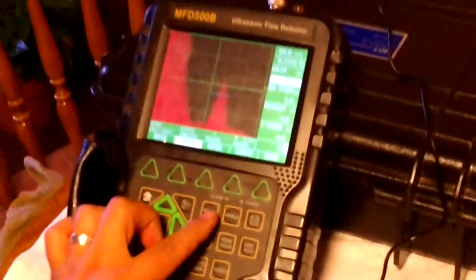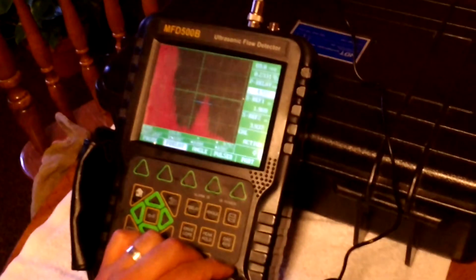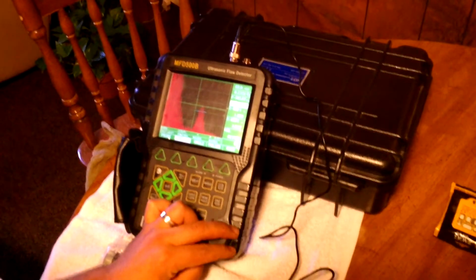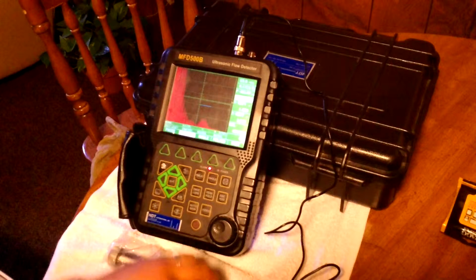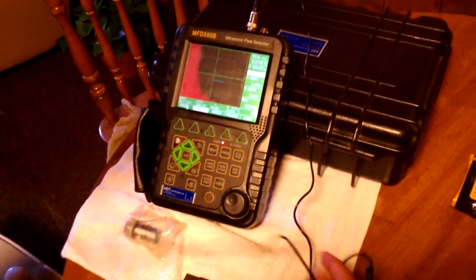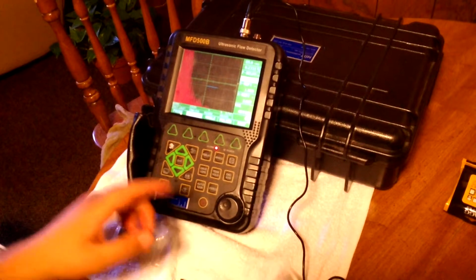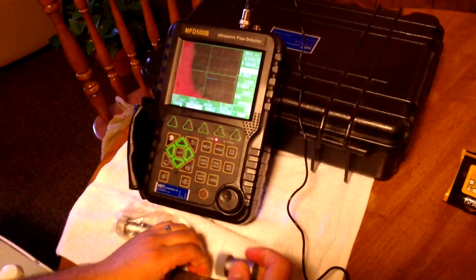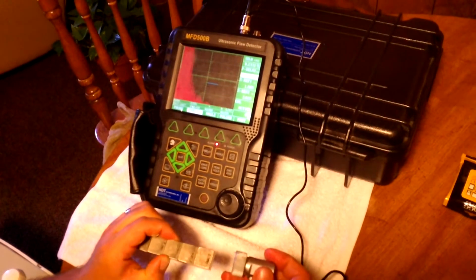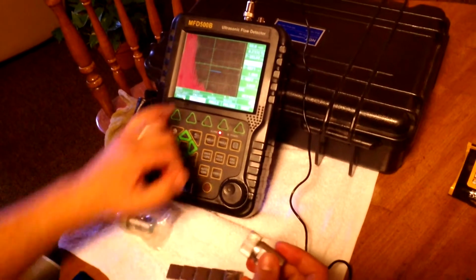Now what I do is calibrate the device. I should make sure that this number is showing up as half an inch. Since I already know that my calibration block is half an inch thick, I will change the probe delay until I get exactly half an inch, or as close as possible. Now the probe delay is the delay that is in the cable and the delay in the probe itself. By calibrating that, I have a better calibration for the device, and I get accurate numbers.